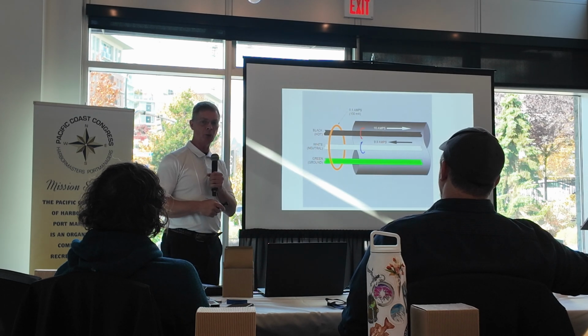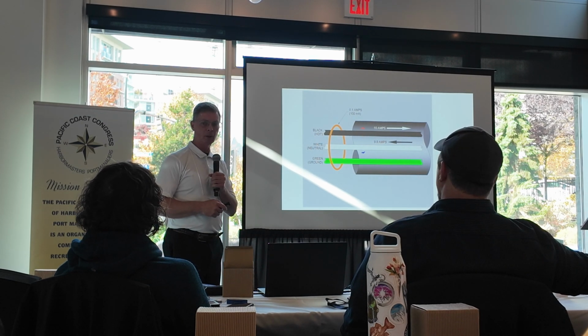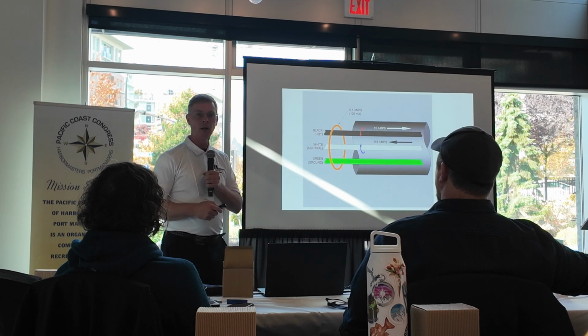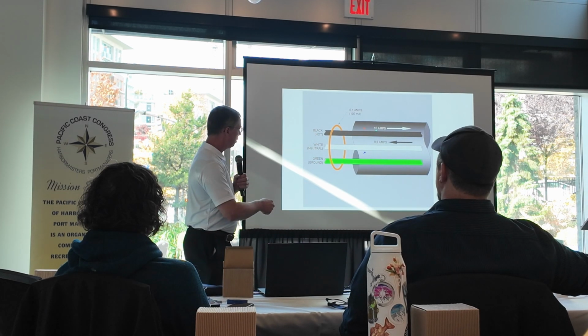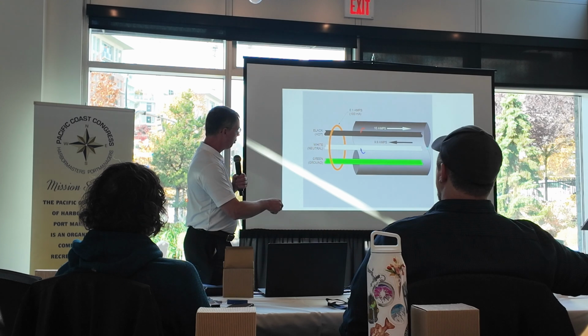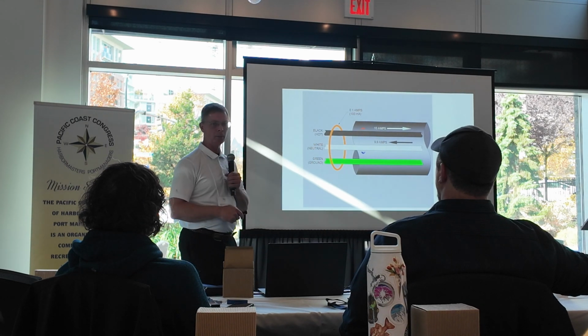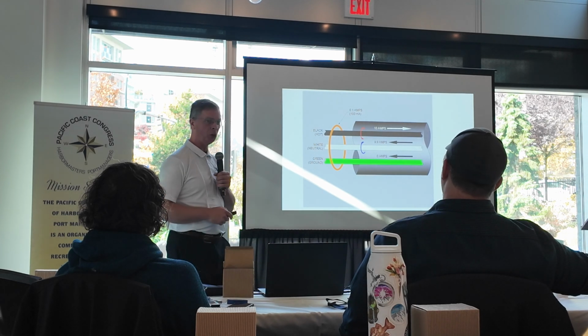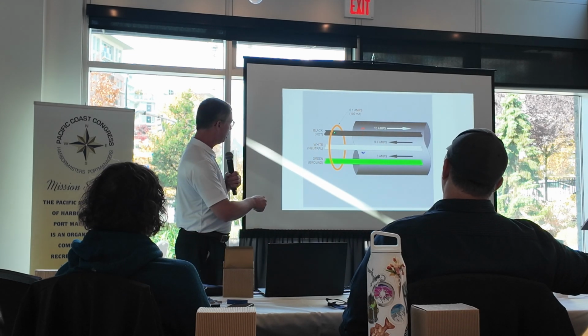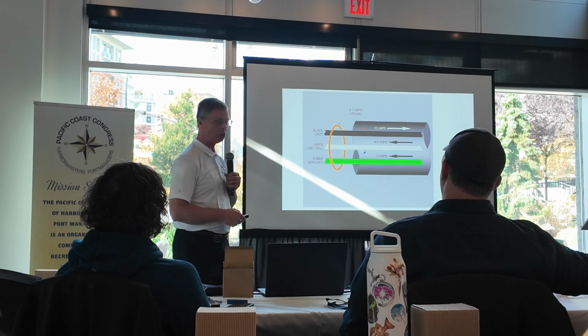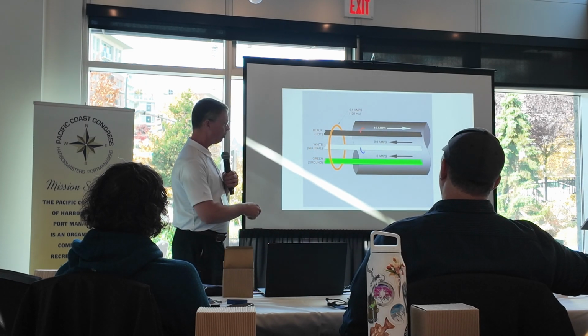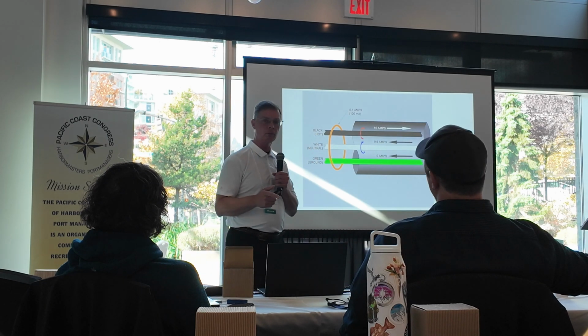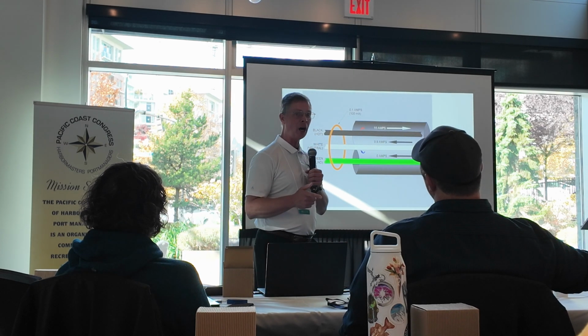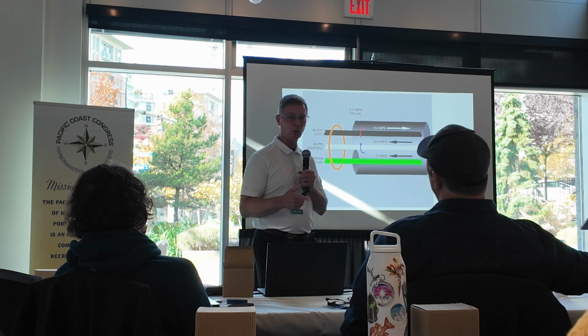What's happening in this situation? There's the external influence. What's that? There's an external source. Okay, because you think about it, there's 10 amps going, here's 9.9 amps going back. Is there anything on that green wire? There's not. That green wire has 0 amps on it. Because I'm reading a differential of 0.1 amps, and I can clamp around that wire and see it, but there's nothing here. So where is that current? It's got to be in the environment somewhere, because it's not on the cables.